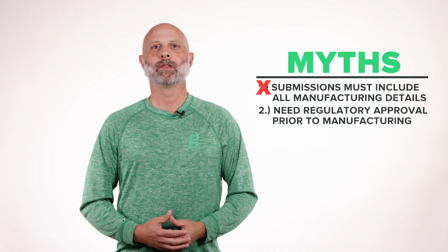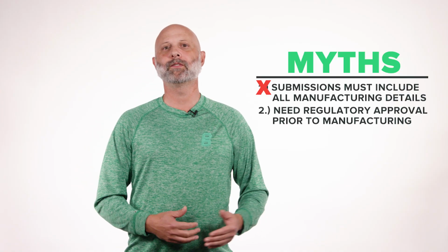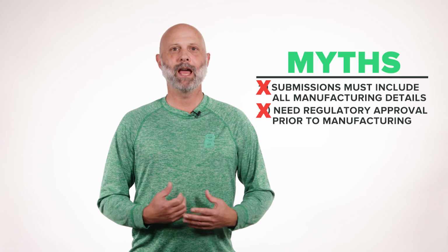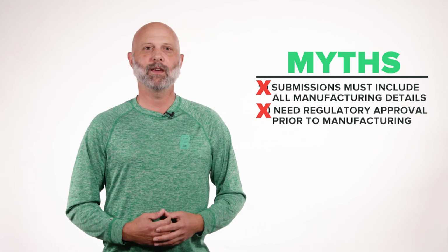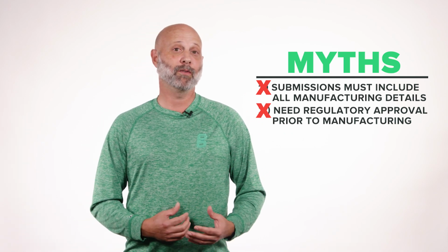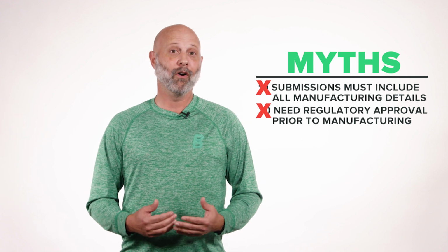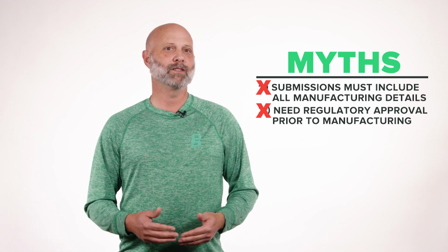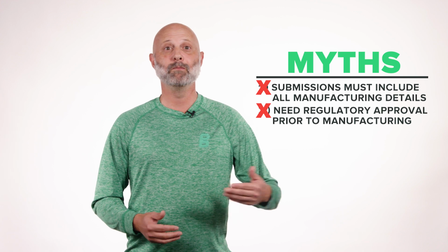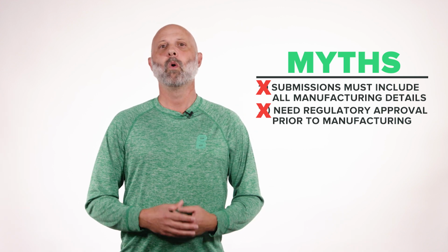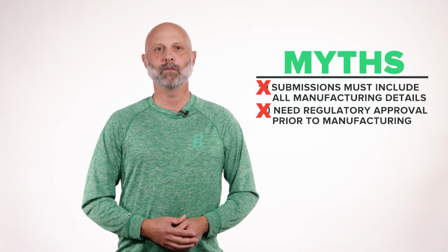Myth number two: you have to wait until you receive clearance or approval from regulatory bodies before you can begin manufacturing. Just not true. The reality is, according to FDA's 21 CFR Part 820, you don't have to wait at all. In fact, the wording in this regulation shows that it's expected you'll be moving into manufacturing while awaiting a response to your submission.